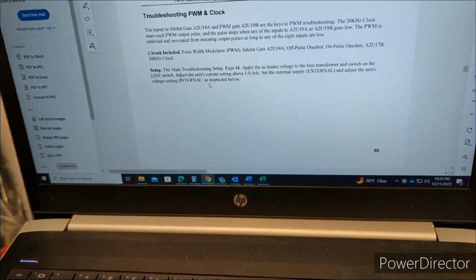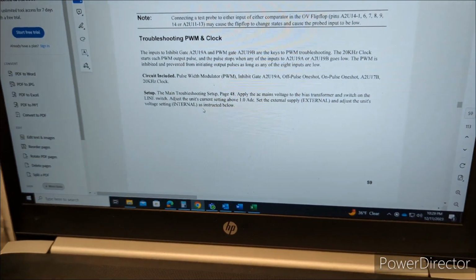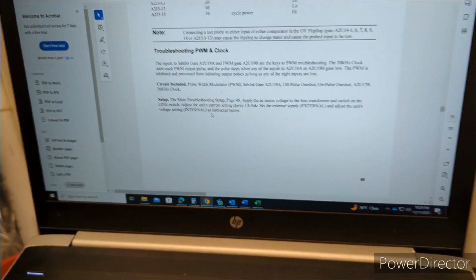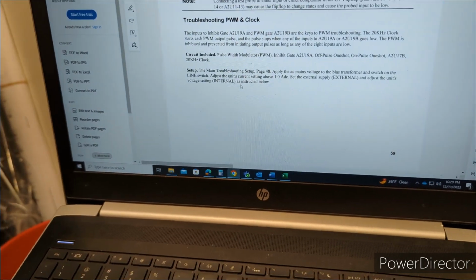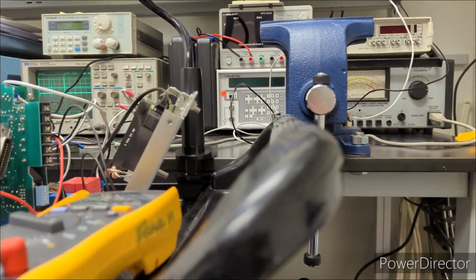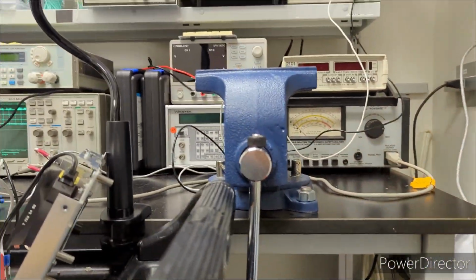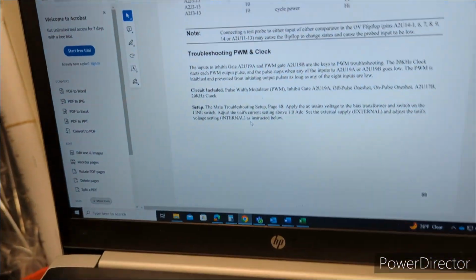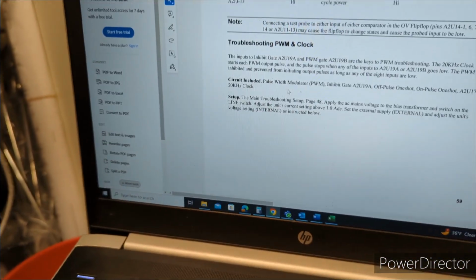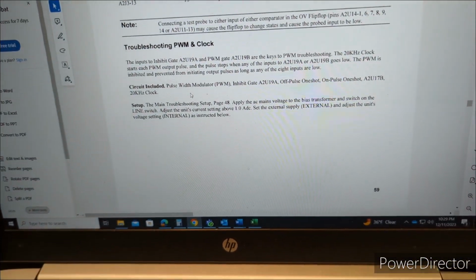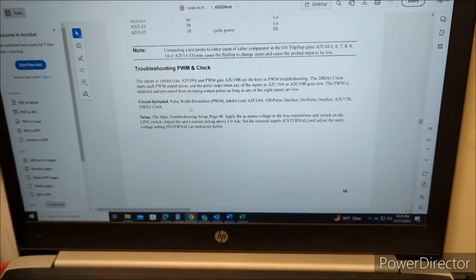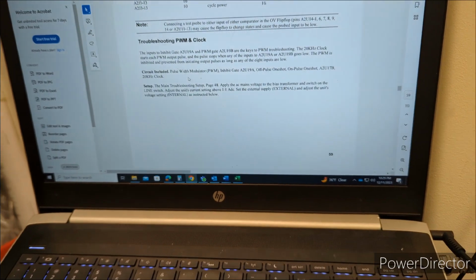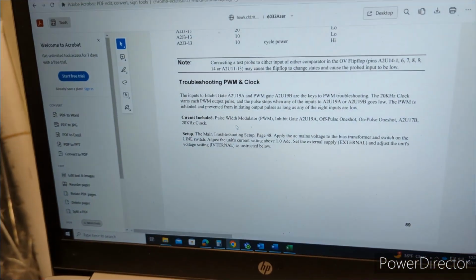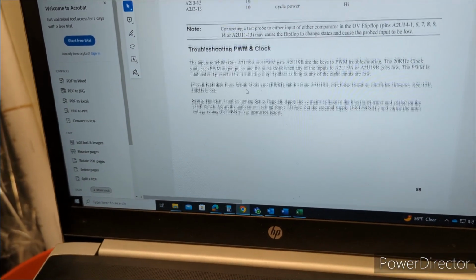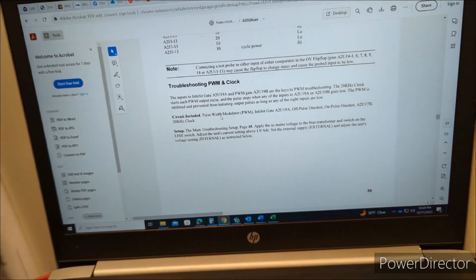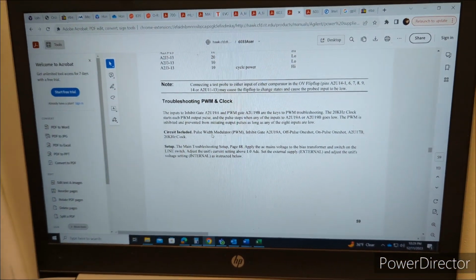Calibration is going to have to wait. I was looking at that, and it does require a GPIB controller, which I do not have. I did order one, because a lot of my equipment does have a GPIB interface, which is quite common on older equipment, so it'll come in handy for a number of reasons. But we'll have to wait for it to come in, because you basically put the supply in different configurations using that controller. That isn't possible using the front panel controls. But let's do some of these, and if we find something wrong, that'll lead us in another direction. Let's get started.